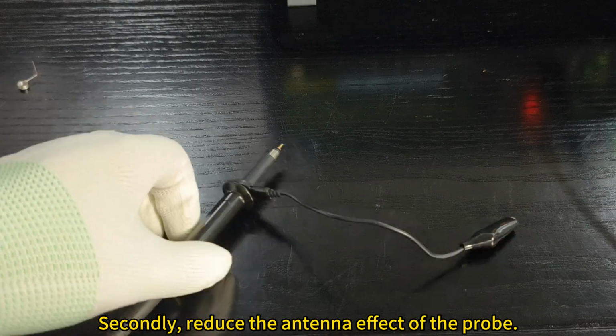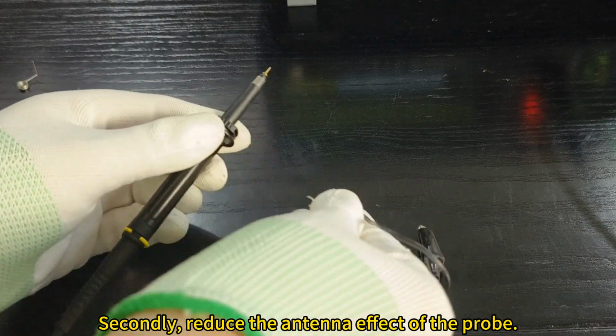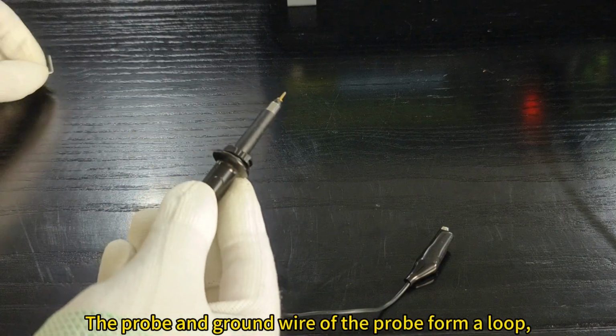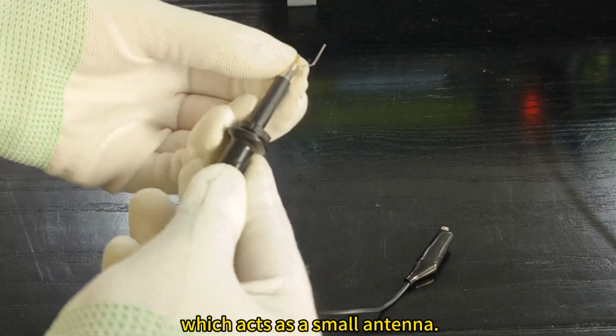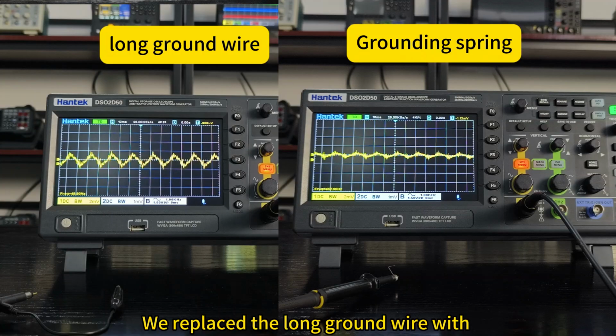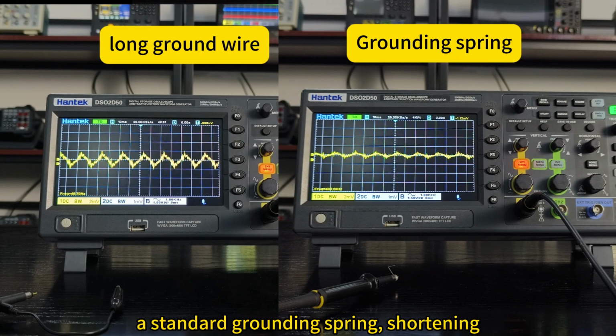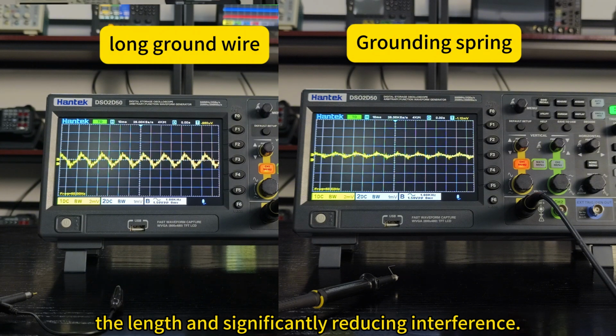Secondly, reduce the antenna effect of the probe. The probe and ground wire of the probe form a loop, which acts as a small antenna. We replaced the long ground wire with a standard grounding spring, shortening the length and significantly reducing interference.